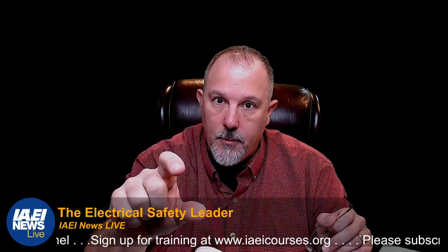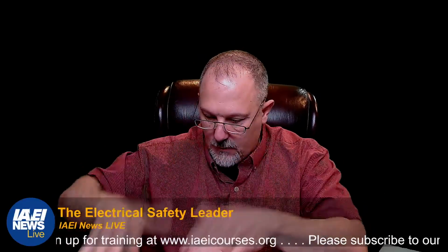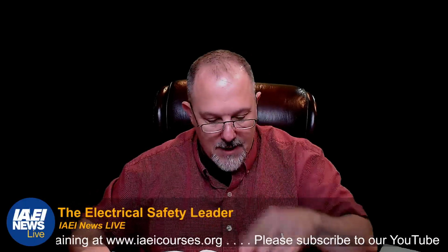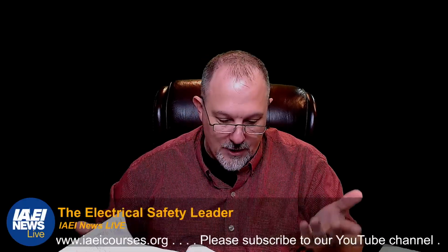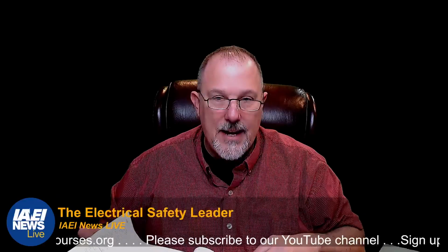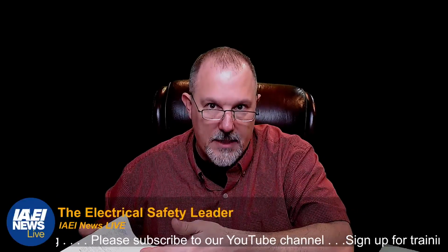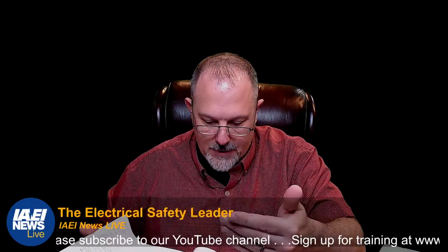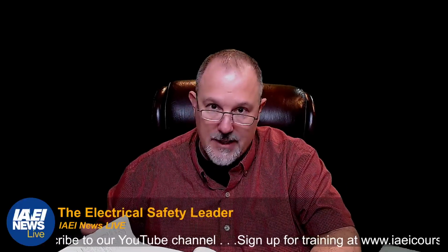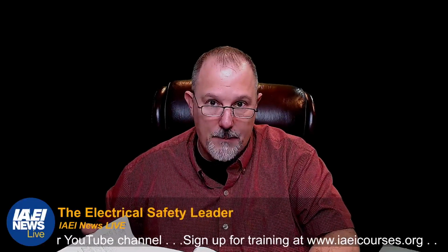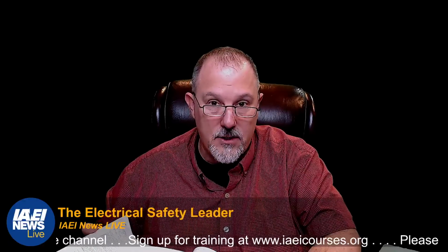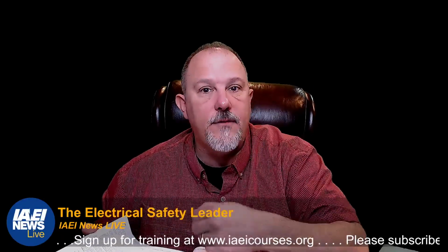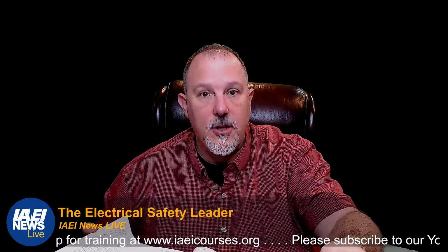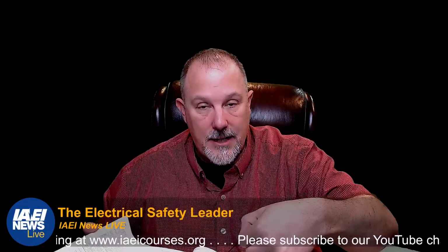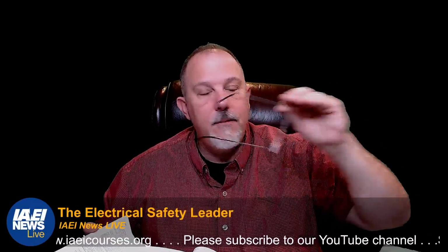So with a panelboard, again, you're going to focus in on 408, but in reality, you can't forget about Article 240 for overcurrent protection. You can't forget about anything else, the proper sizing of the breakers on that panelboard for the conductors that are connected to it. The terminations, 110.14. You can't forget about terminations and the requirements for the installation.